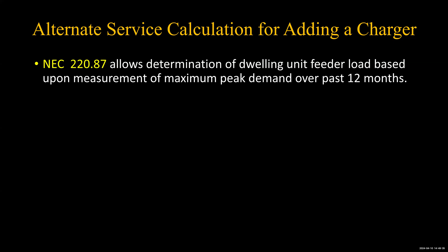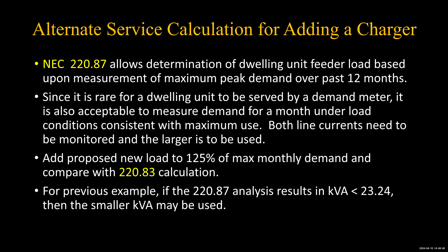And for my condominium here, for example, we've got 1,600 amps of house load, not the units, but just the hallways and the elevators and the air conditioning and stuff. And we're only using about 290 amps of that 1,600 amps. All the rest of that is left over and could be used for charging electric vehicles using the 220.87 method. Okay, so in any case, 220.83, 220.87, use whichever one works, whichever one will give you the best answer. Where do you tie it in? Maybe it goes right to your main distribution panel, but maybe it has to go elsewhere.